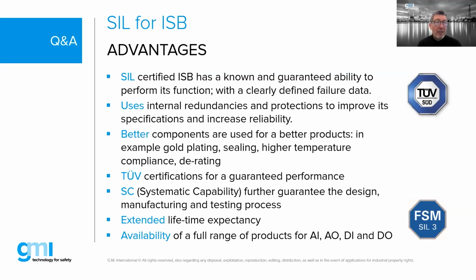Where it would really matter is if we have a fire and gas system that needs to comply with functional safety requirements. Then having a SIL-rated product as part of that overall system is absolutely important. Is it a good idea to have it for other applications? It doesn't hurt. What we're talking about with SIL ratings is that the reliability of our products is basically validated. That's really the whole thing.